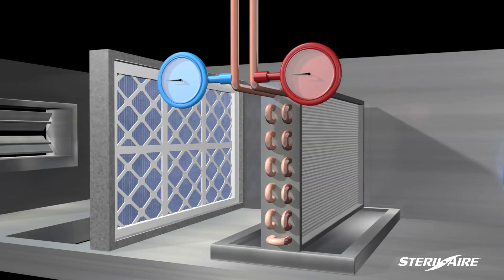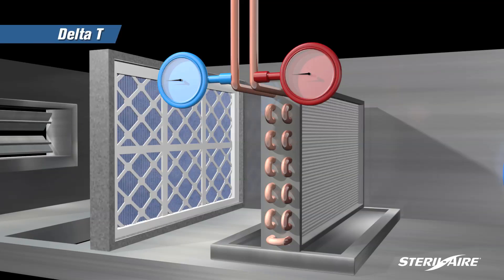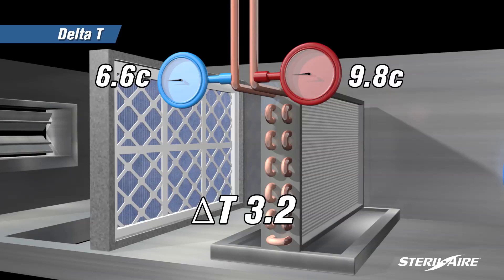The efficiency of the coil can easily be measured by checking the delta T of the coolant, entering and leaving the coil. Before sterile air, the chilled water supply temperature was 6.6 Celsius, and the return 9.8, with a delta T of 3.2.